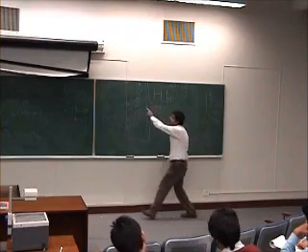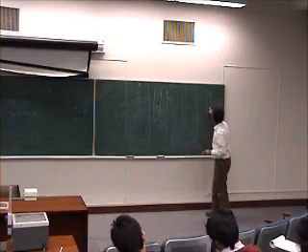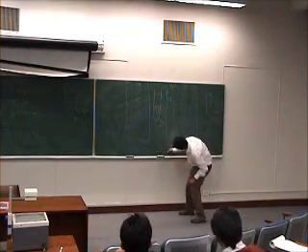Now this is an inductor, and this is the capacitor, which is a variable capacitance. Suppose you applied a field B naught of 3 tesla, and then you found the Larmor frequency is 126 megahertz. Now you tune this coil: you have a fixed L, you tune the capacitance such that the frequency turns out to be the same as the Larmor frequency. And you connected this to a function generator which is tunable. You gave it 126 megahertz.